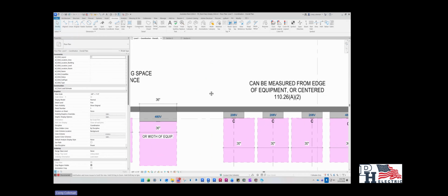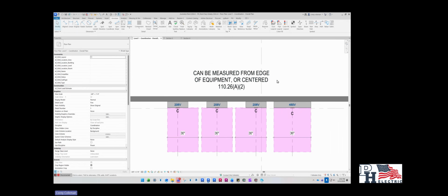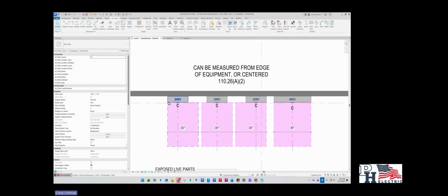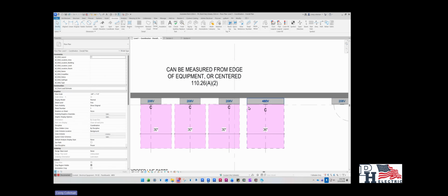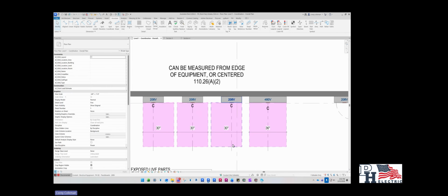Next, these clearances can be measured from the edge of the equipment or from the center. As you can see for this panel, you can measure 30 inches clear from the left side past the panel. This one you can measure from the center of the panel. It can even be offset a little bit, as long as there's 30 inches width-wise in front of that piece of equipment, you're clear. Unless that equipment is larger, as you can see here, these are still technically being measured from the edge. It can't be offset. So it has to be the same width of the panel for larger pieces of equipment.